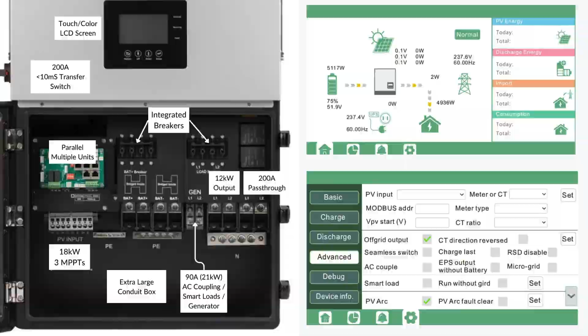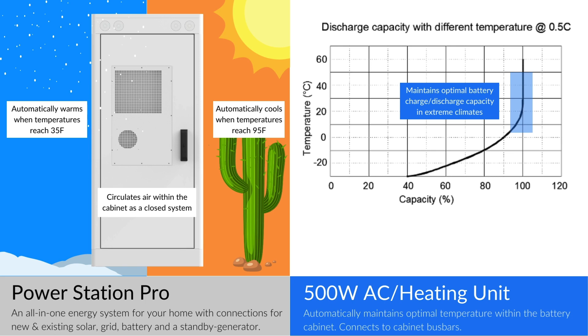For PowerStation Pro, we also offer a 500 watt automatic AC heater. The unit only operates when temperatures reach 95 and 35 degrees. Otherwise, the unit is on standby. This ensures the batteries are protected from temperature extremes, which improves performance and longevity. Currently, these units are an optional add on, but later this year, they will be included with every PowerStation Pro system.